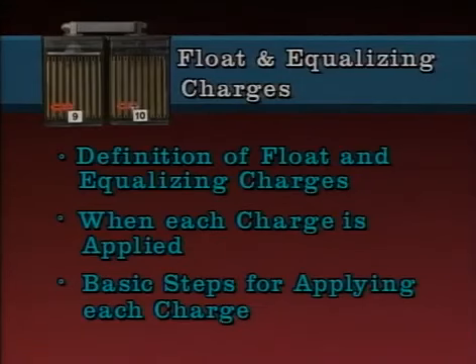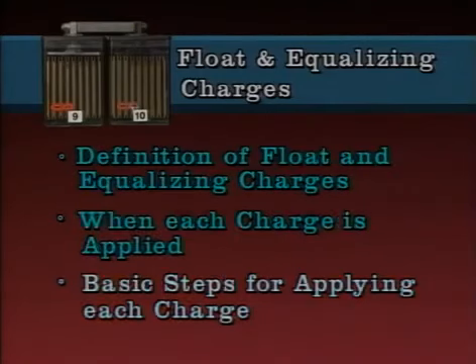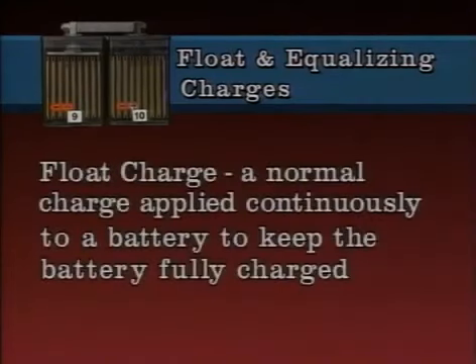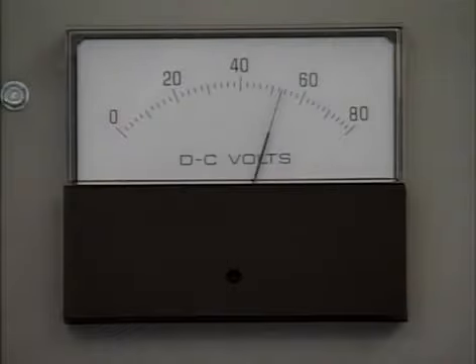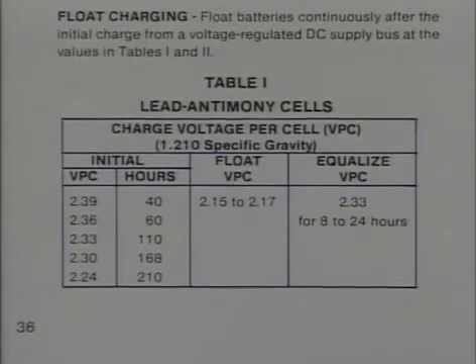The key points covered include the definition of float and equalizing charges, when each charge is applied, and the basic steps for applying each charge. A float charge is a normal charge applied continuously to a battery to keep it fully charged. The voltage is floated at a fixed level slightly above the normal open circuit voltage, allowing the battery to draw just enough current to overcome its self-discharge losses. The float voltage setting is typically specified in cell manufacturer instructions or by company procedures.